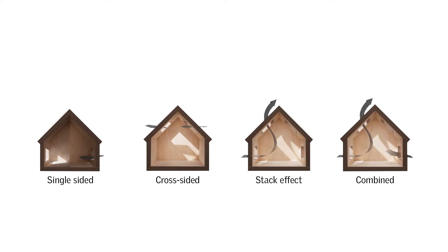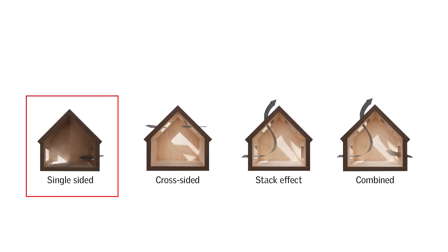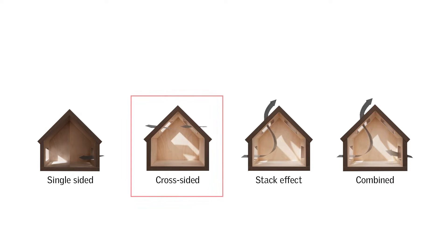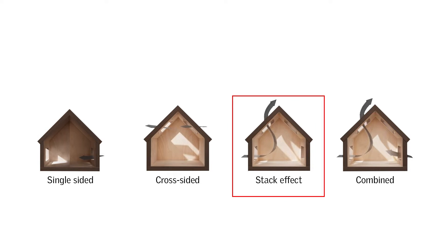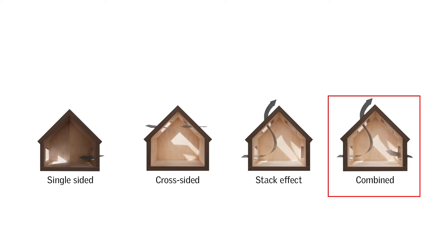Depending on the number and location of the openings, several natural ventilation effects can take place in a building. Single-sided ventilation occurs when all the windows or doors that are open are located on the same external facade. Cross ventilation occurs when windows or doors that are open are located on more than one external facade. Stack ventilation, also known as chimney effect, occurs by having vertical distances between the inlet and outlet openings, enhancing the buoyancy effect. Combined ventilation is when cross ventilation and stack effect occur simultaneously.